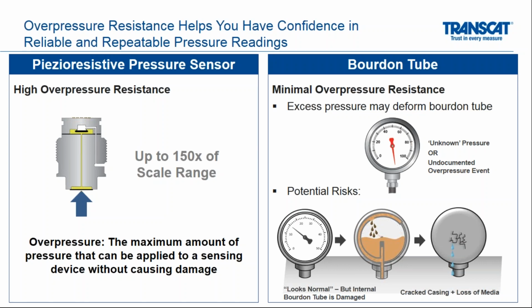Again, with the bourdon tube technology, oftentimes there's minimal overpressure resistance. It's designed with mechanical linkages that are only meant to handle a certain span of pressures, and if you go beyond that, you've bent that bourdon tube or you've bent a linkage or something, so that not only can you not read the gauge correctly, but again, there can be damage, there can be cracks in the gauge, etc.